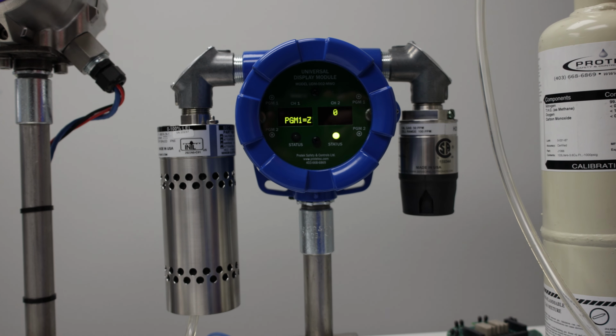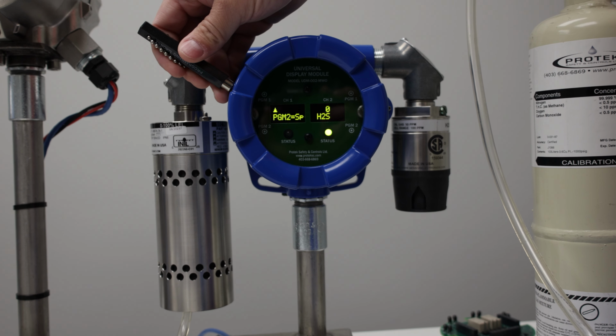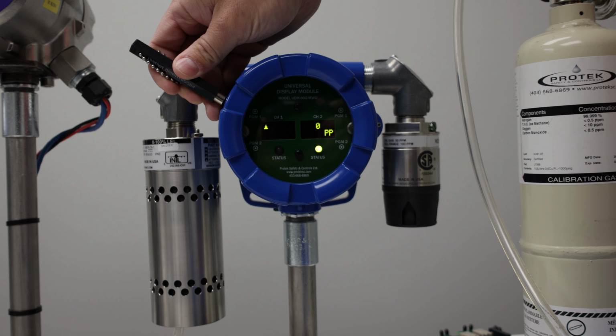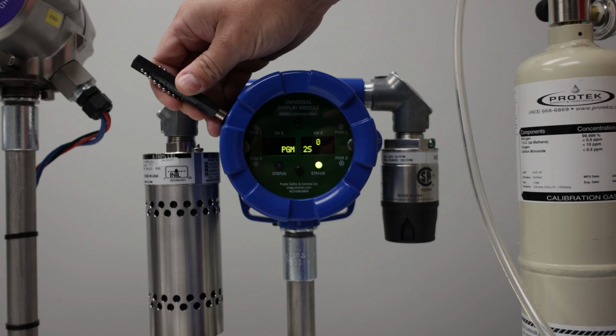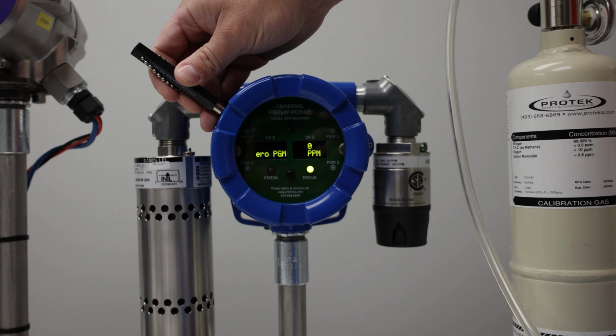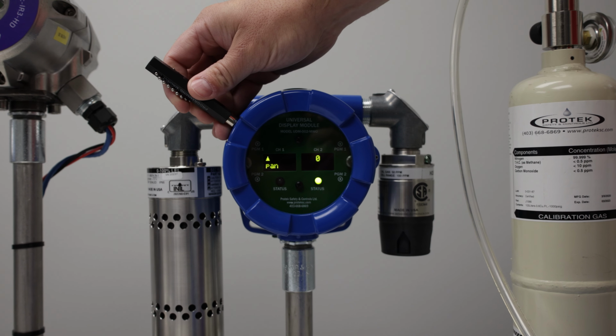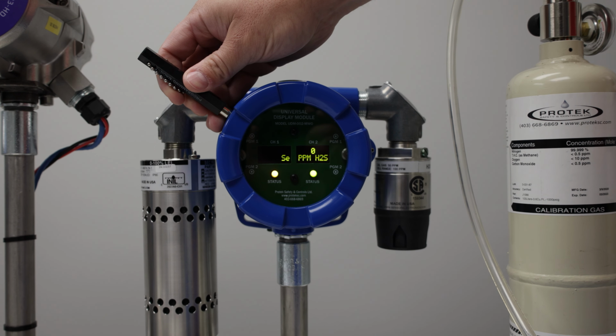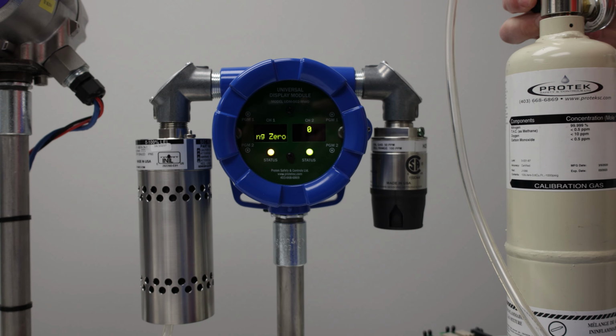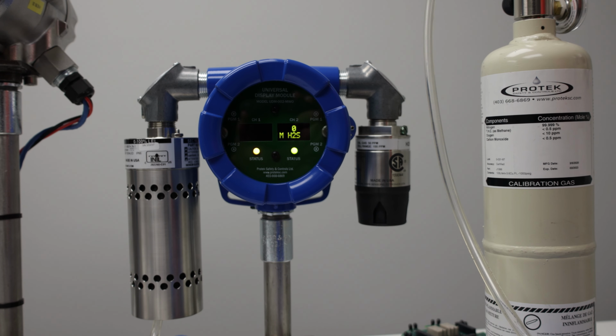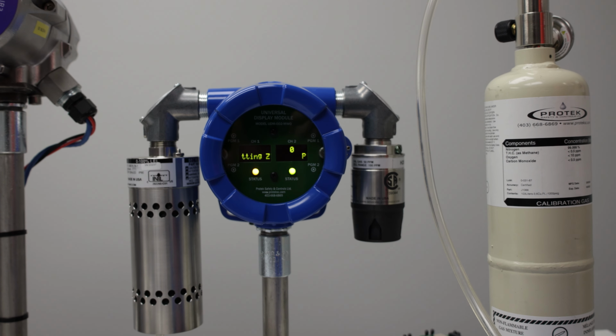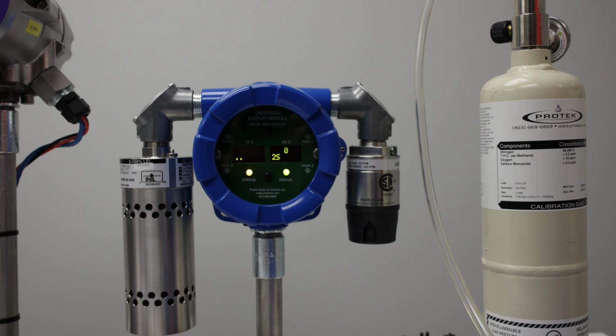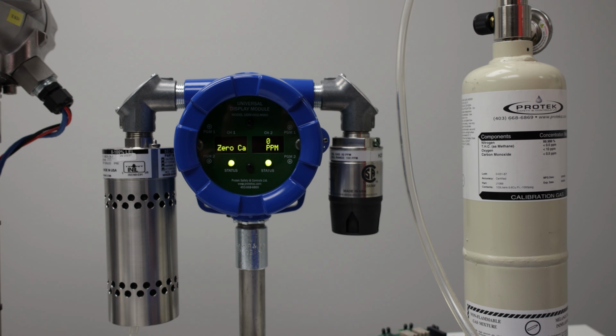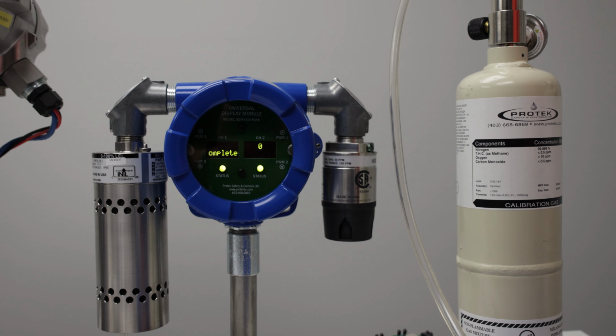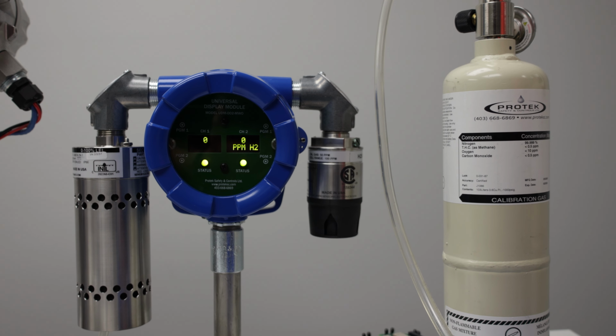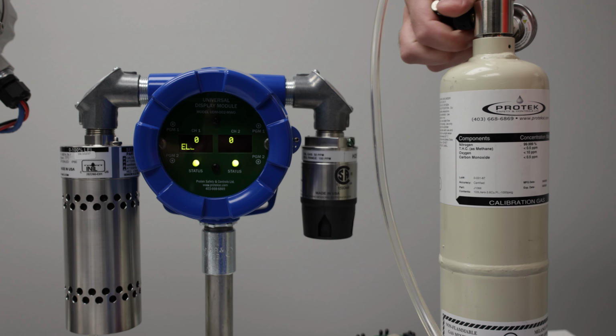You've entered calibration mode. Program 1 is a 0, program 2 is a span gas. So I'm going to hold it on program 1 here till the arrow comes up and goes away on its own again. And now we're doing a 0. So I've got this calibration gas open, which is 0% methane, and we're setting the 0. So we're halfway through the calibration of this device already. We're applying a known concentration, telling it to reset its values. Calibration complete, we remove the cal gas. So 0 cal is done.